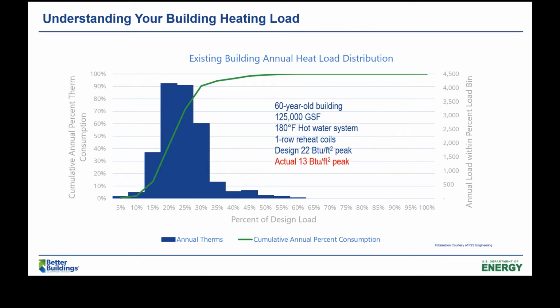There are so few hours running between 45 and 60% that you could probably meet those loads by setting up the temperature a little earlier in the morning with some preheat. There are definitely ways to think about shifting those loads. But 90% of the heat in this building is expended at 30% or less of the load, so if you're thinking about going to a heat pump system, you might think you've got to meet 100% of design load.